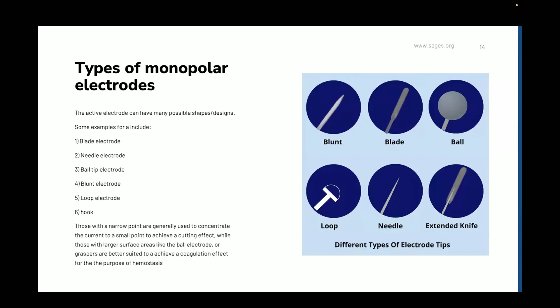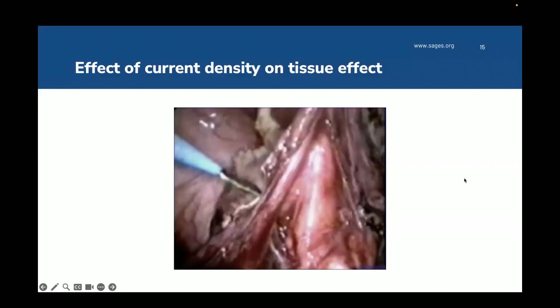Well, this is an example of a video where the surgeon is using a consistent power throughout, but when he touches the tissue with the flat part of the instrument, you get a coagulation effect, versus when he uses the sharp edge or the smaller edge, we get a cutting effect. So this is an example of how same mode, same power, but different tissue effects based on the surgeon's manipulation of the instrument.